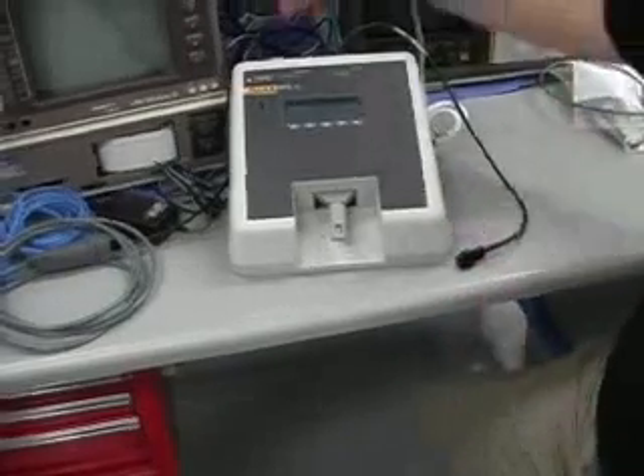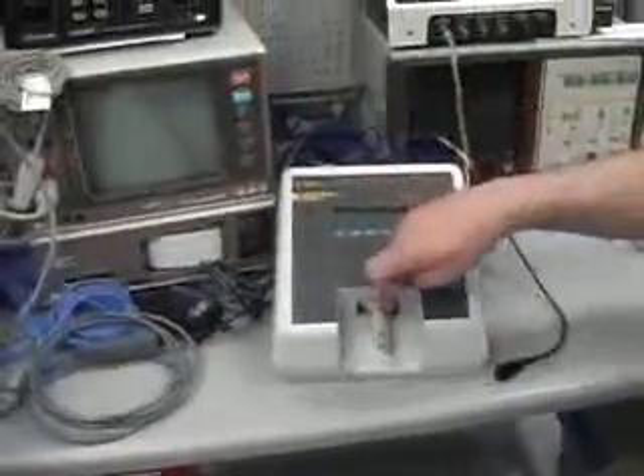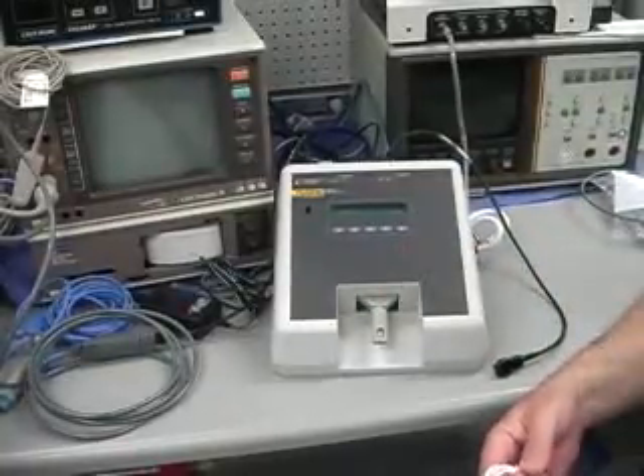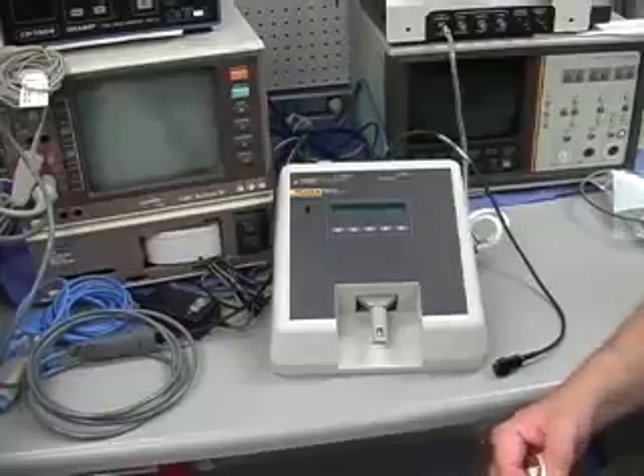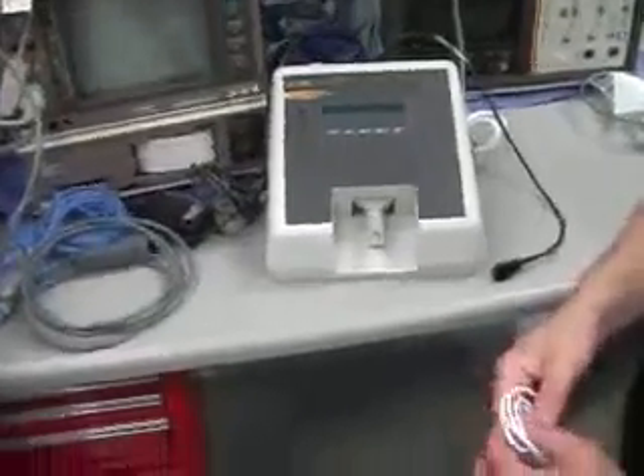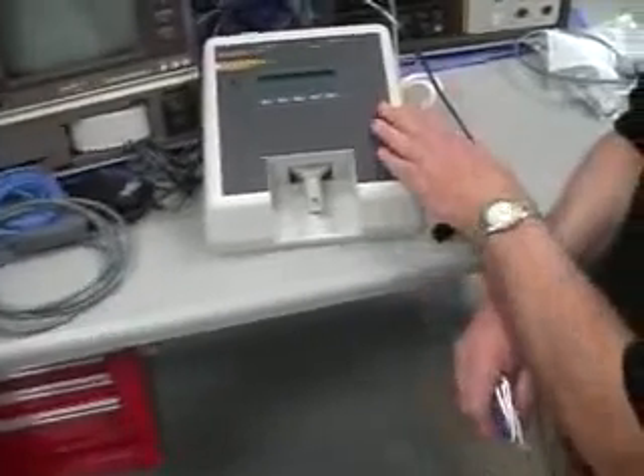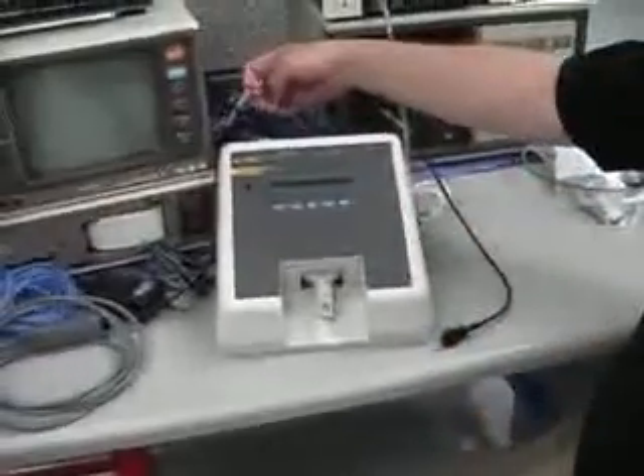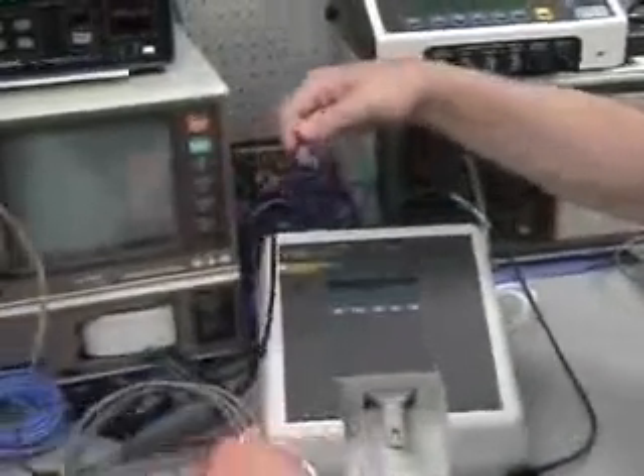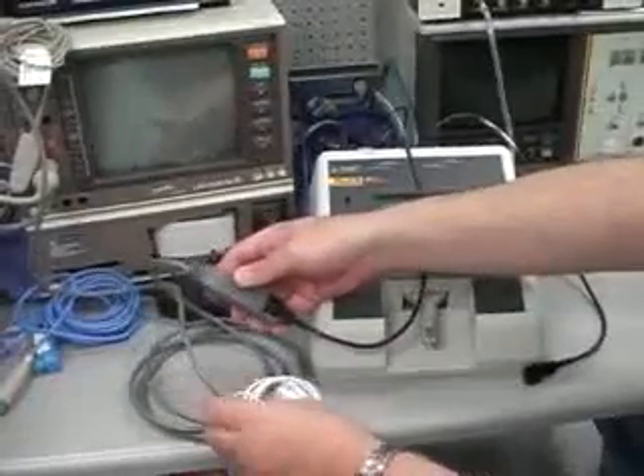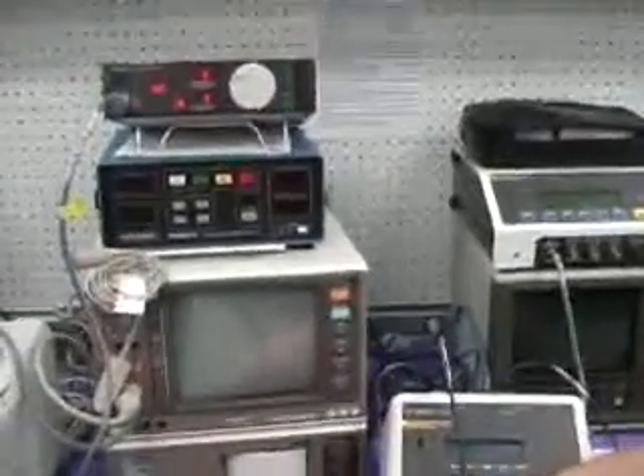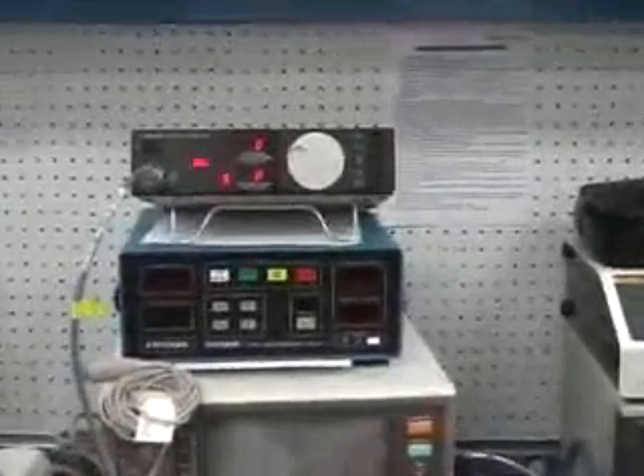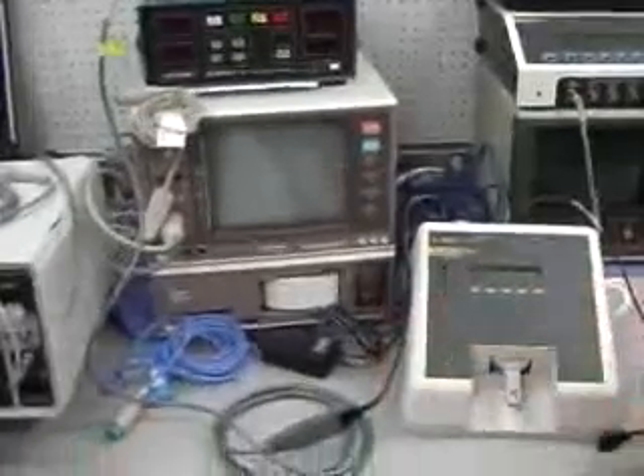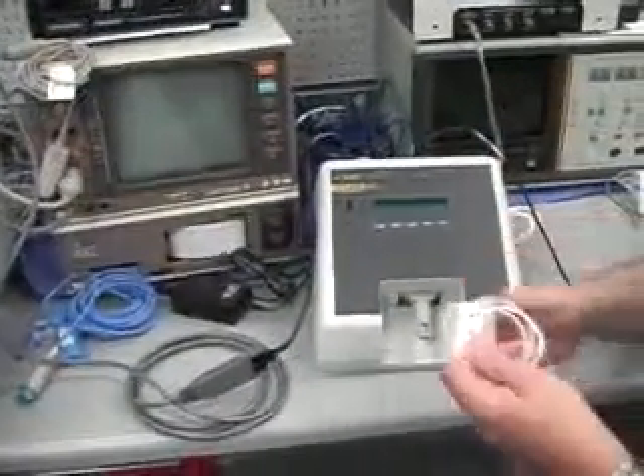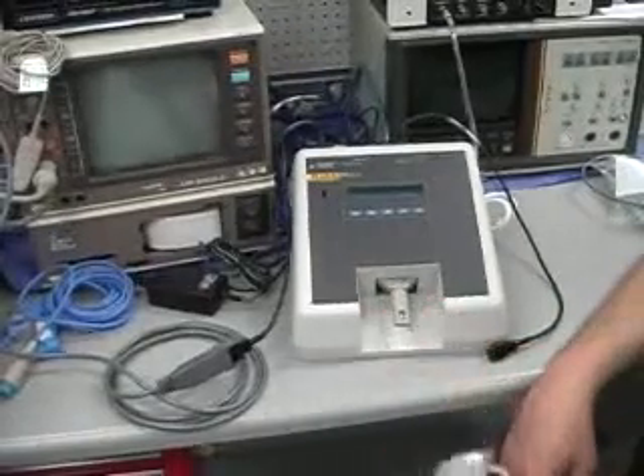Right now we are running the electrical simulation. We're having some problem with the optical, but the electrical simulation is looking like it is working quite well. From a basic operational perspective, once you turn the device on and you've hooked the electrical simulation cable to the instrumentation amp on the Nellcor, which is one of the earlier Nellcor series monitors, we're doing direct electrical simulation. So you don't have any of the variations or difficulties with using the optical finger, and it is a more repeatable test.